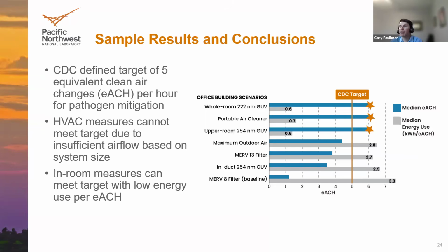Whereas on the other hand, the in-room measures were able to complement the baseline ventilation from the HVAC system to then meet the CDC target by inactivating or filtering particles directly in the zone themselves. And those in-room measures of whole room or upper room GUV, as well as portable air cleaners, were able to meet the CDC target of 5 EACH for offices with a low energy use per EACH as well.